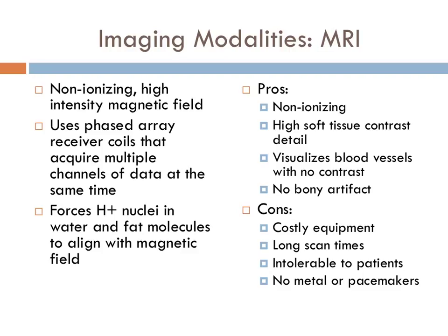And a lot of times, it's not just the cost that poses a problem of getting the MRI into your building, but the size. Depending on where the MRI is located in the building, it can actually be a pretty big feat, knocking down walls and doing other construction projects in order to get the MRI in the building.